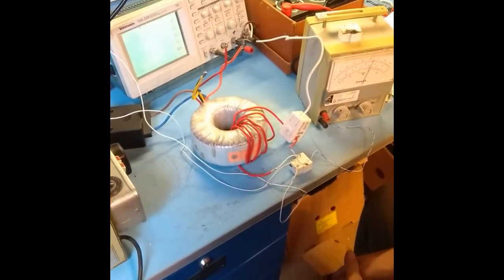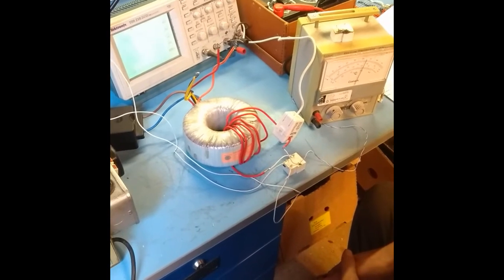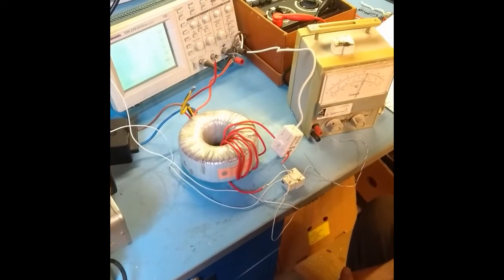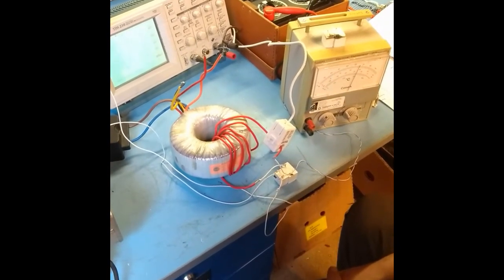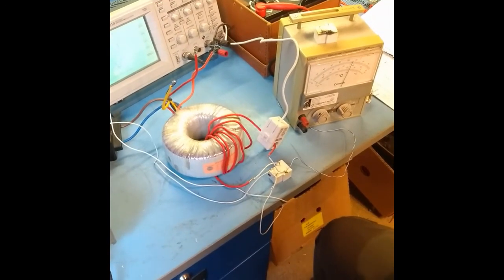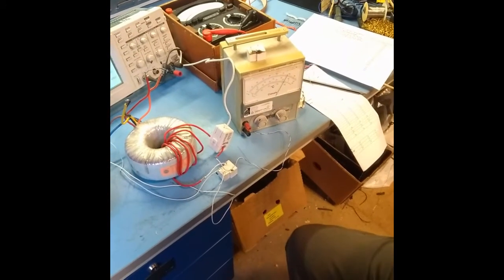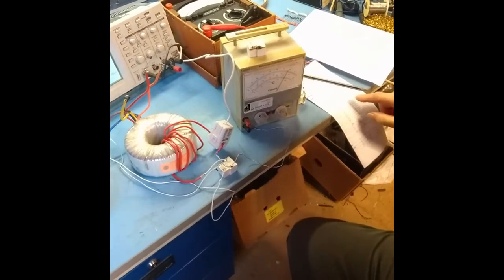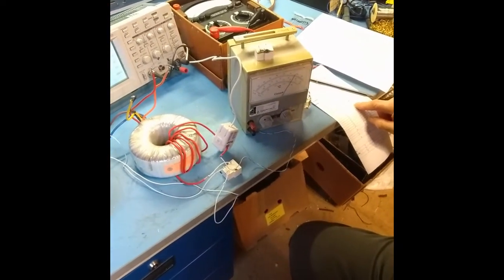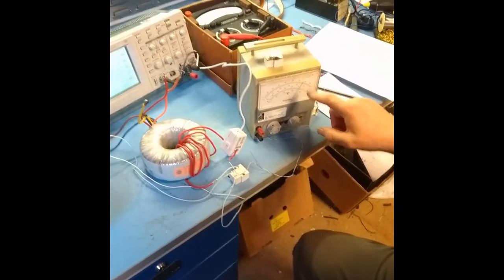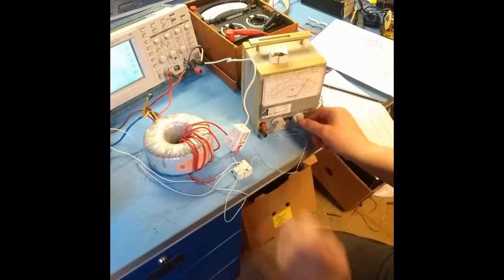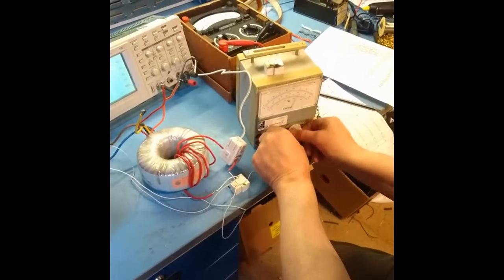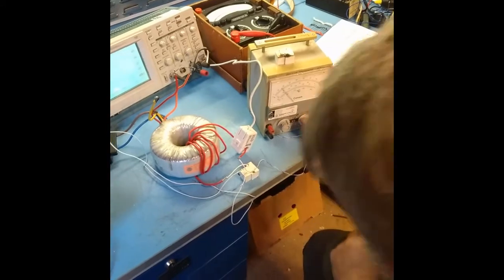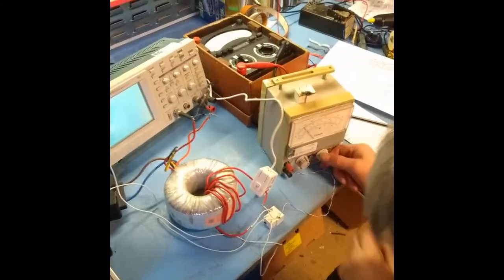So the temperature is going up again. It's now above 100 degrees C. It's 110 degrees C. Give it some time to stabilize. So we're now at 134 degrees centigrade on the pin with an ambient of 11.2.